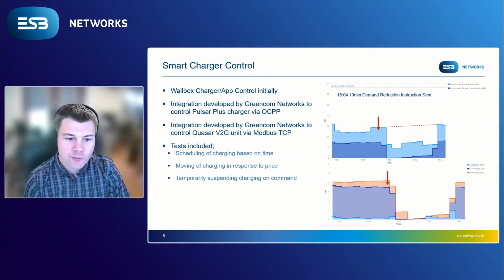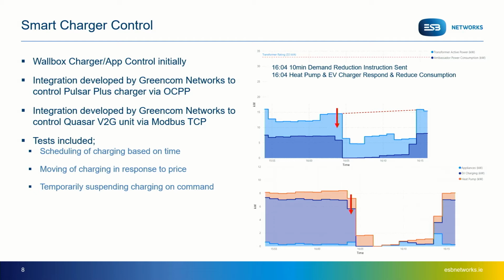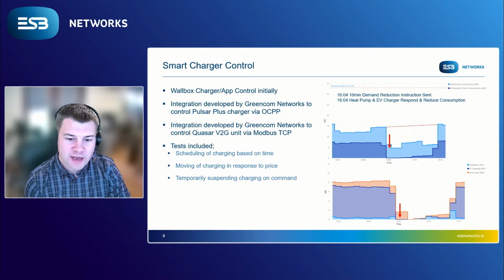In this example, a command was sent at 16:04 to the property, and by 16:05, the EV charger and heat pump had reduced their consumption. In total, 7 to 8 kilowatts of controllable demand was suspended for a 10-minute period. At the same time, the installed battery storage system also provided 2.5 kilowatts into the home, and the excess was sent to the grid, and the resultant power reduction observed at a transformer level was approximately 10 kilowatts, that's shown on the top right chart.